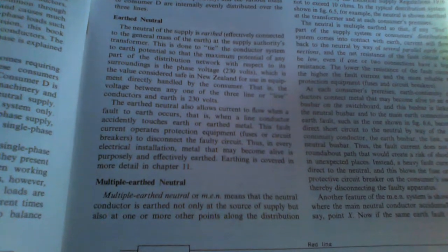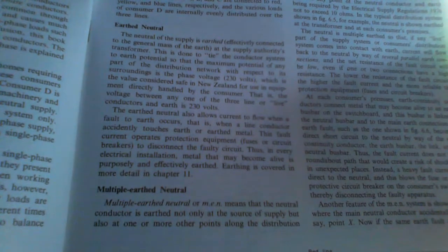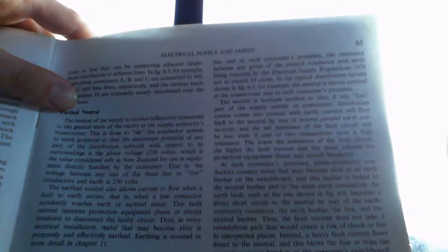But this is how the multiple earth neutral, MEN, works: the neutral conductor is not only earthed at the source of the supply, but also at one or more points along the distribution line and in each consumer's premises, for the resistance between the point and neutral conductor. Earth, but being required by the electrical supply regulations 1976. I told you this book is very old, but the theory is still the same. Not exceeding 10 ohms, but now probably the number has dropped, maybe because the codes have changed over the years since 1976. I'll tell you now, if you follow that code, I advise you please to stop.